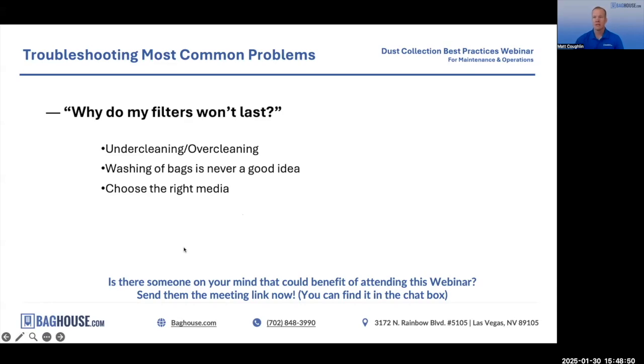So what will cause them to fail early, or that end of life failure to not be as long as it should? Your cleaning system settings are important. You want to set your cleaning system timer so that it's cleaning them enough to remove the dust cake and keep your differential pressure low, but it's not just cleaning them all the time, because essentially you're sending a shock wave of compressed air. It's flexing the bag, and over time you get a fatigue failure, and the bags will wear out.